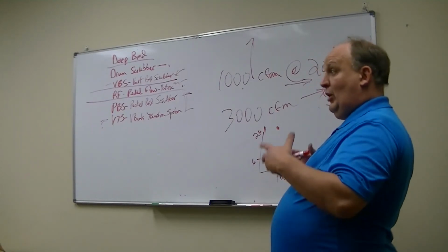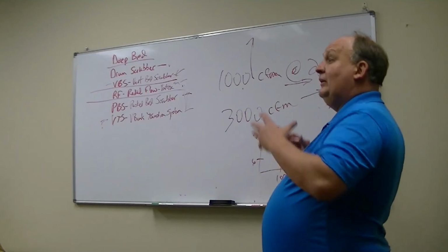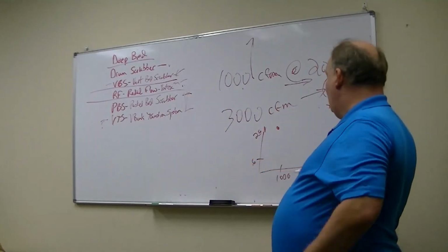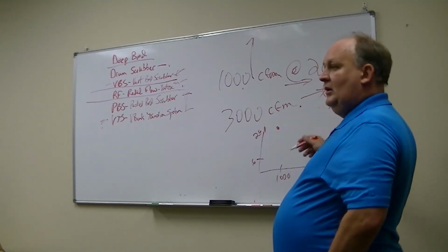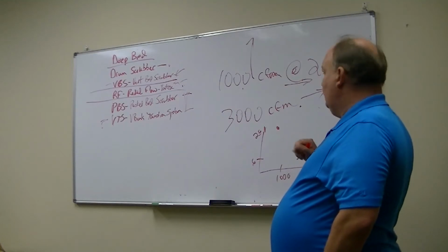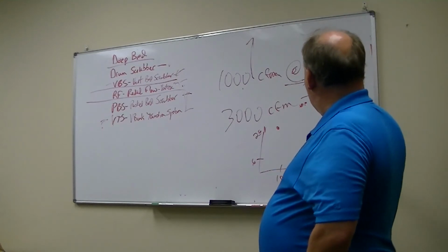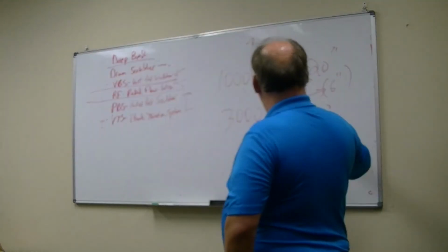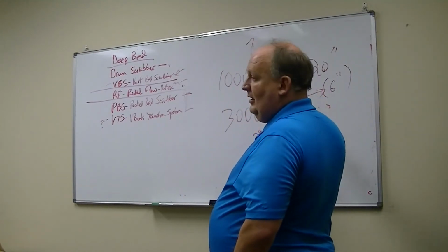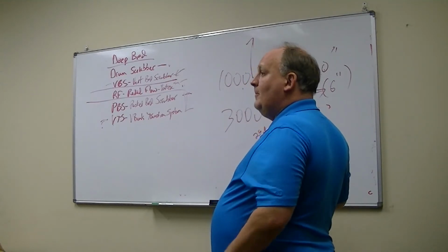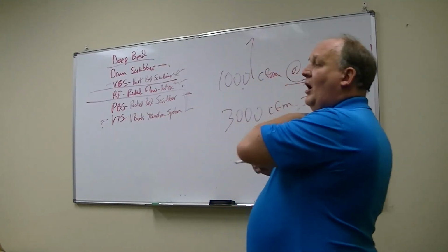Kind of type thing. So you're probably gonna have to put a big motor on there, because that blower's got to have the capability to get to that level, but we're going to set it at this level, okay? And so we'll say, Mr. Engineer, we get out there, we know our stuff, and we're telling you it's going to be 1,000 CFM at 6 inches, okay? But if we get out there and we don't have enough airflow, then it'll be Pure Air's responsibility to change the belts and the pulleys on the blower.